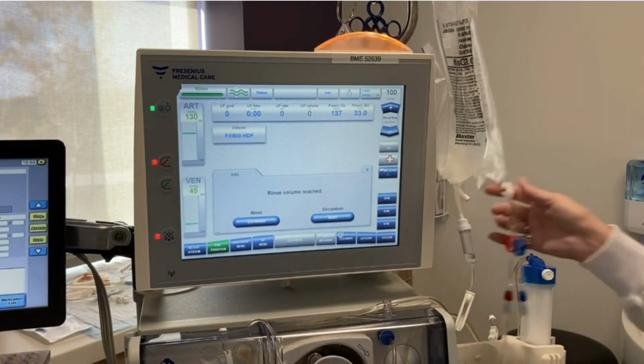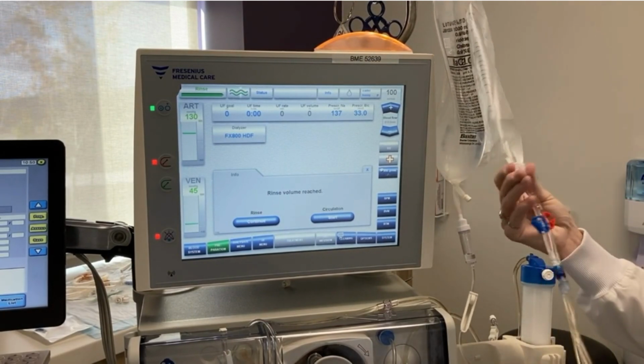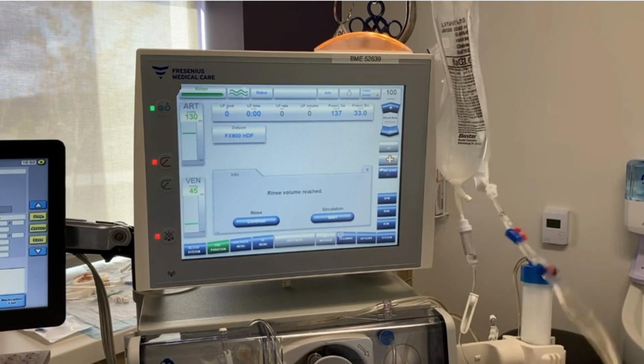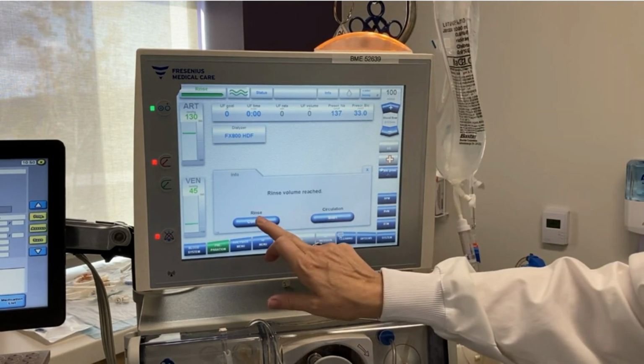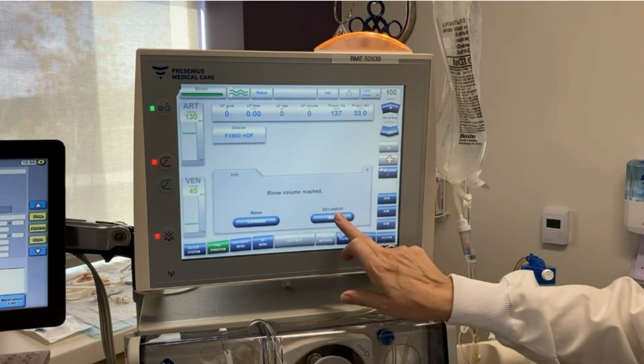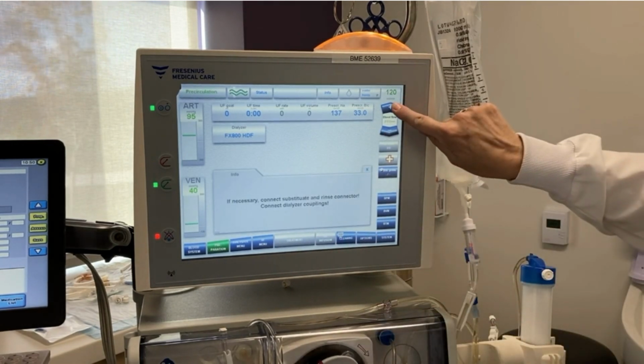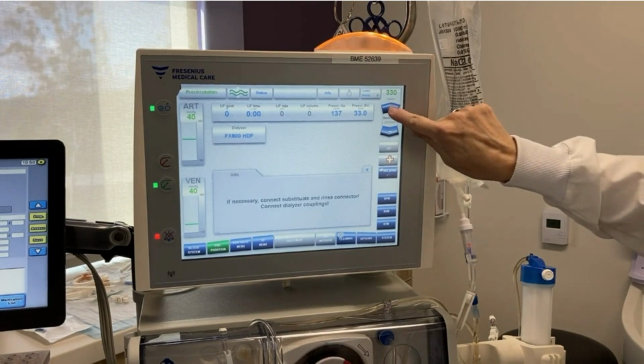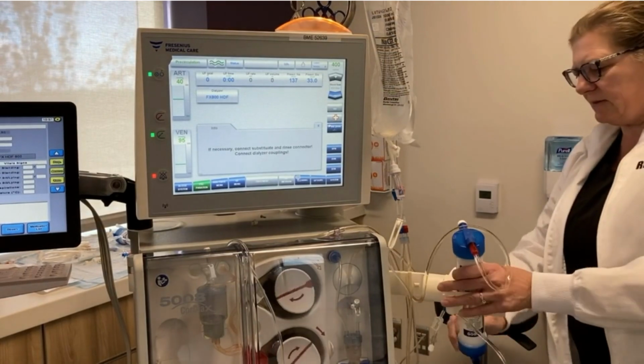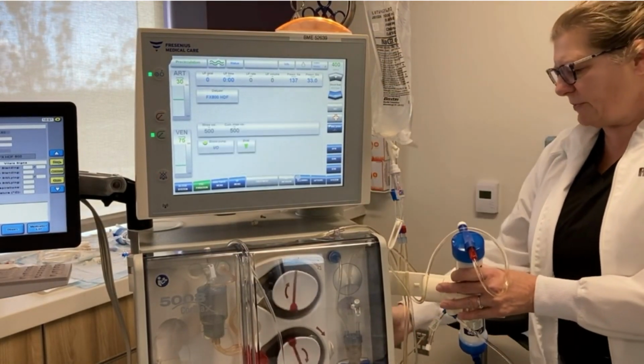Okay, our rinse volume has been reached, so we're going to close off our drain bag, open our arterial line, and put it into circulation and increase to 400 as per your regular setup. Our T1 test is complete, so we can now hook up our dialyzer.